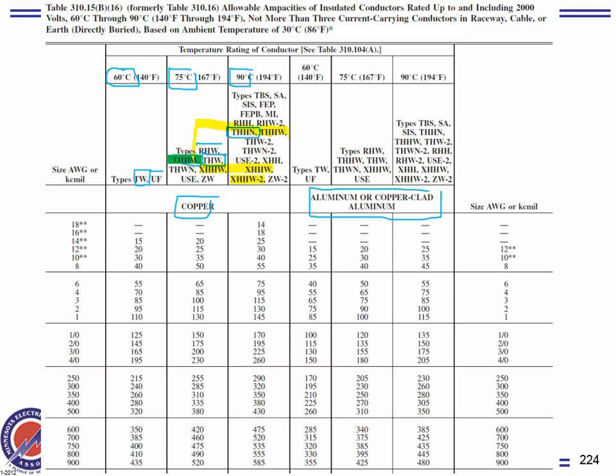Yes? So, they wouldn't tell you. They would tell you a feeder on a roof or an underground feeder. A 4-aught conductor is an underground feeder. How much current can this conductor carry if it's 4-aught underground? 4-aught underground, right here. If it's 4-aught and I didn't say underground, in a building, for derating purposes it can carry up to 260. It wouldn't carry it, but you can use that.